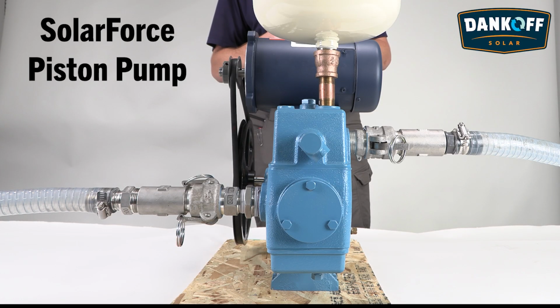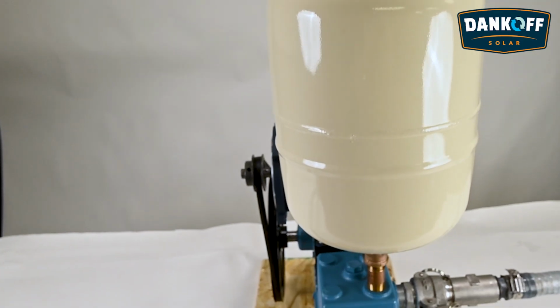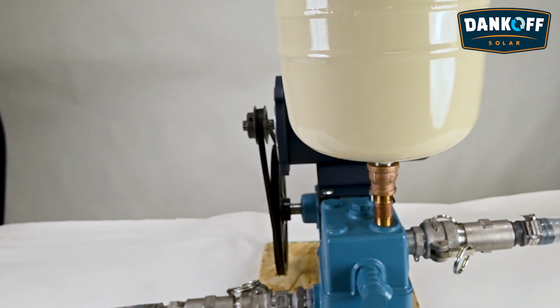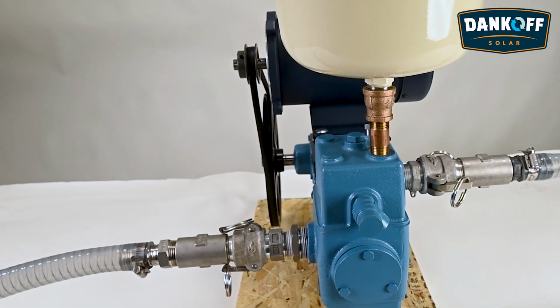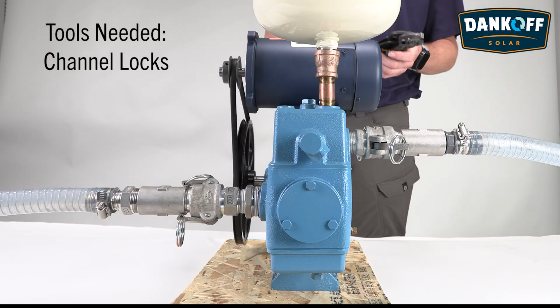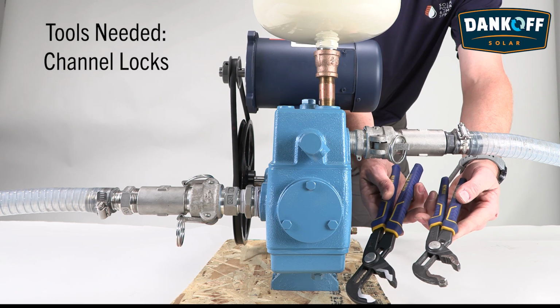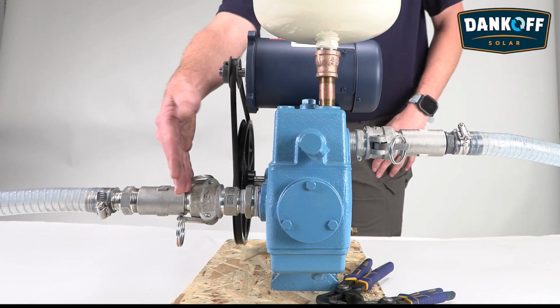We winterize this pump because this case is a cast part. We wouldn't want any freezing inside of it. That could cause a lot of stress fractures inside the mold. Then you will be replacing parts. For this pump, you're going to need a couple channel locks to do the winterization. It's a pretty simple process.